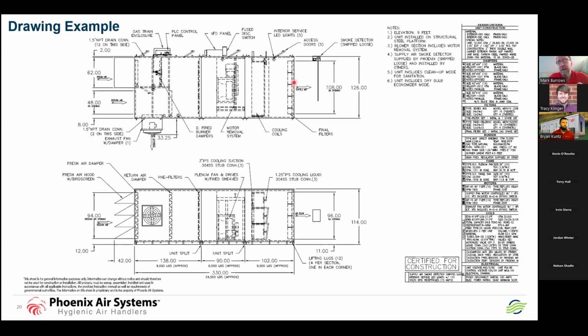What we're typically doing on the final filters is a face velocity, again, of about 550 to 600 on the high end. Most contractors would design for maybe 1,500 to 2,000 feet per minute through the ductwork. So you will definitely see a transition from the large opening that we have of 108 by 96 down to some much smaller configuration for the ductwork.